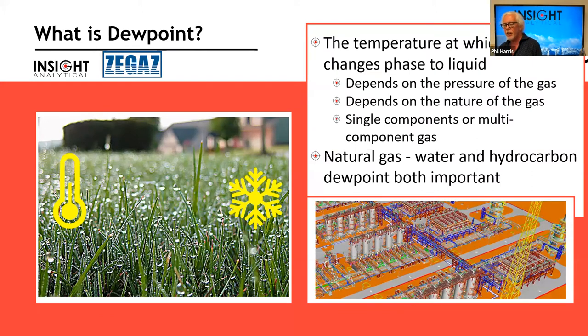So the first thing we want to talk a bit about is, what is dew point? What do we mean? We hear this phrase all the time about dew point analyzers. Dew point is the temperature at which a component in a gas phase stream will change phase and become liquid. We commonly see it in dew on the grass at night, because the air was humid. It got cool overnight, and as it cooled down, water condensed out on those blades of grass.